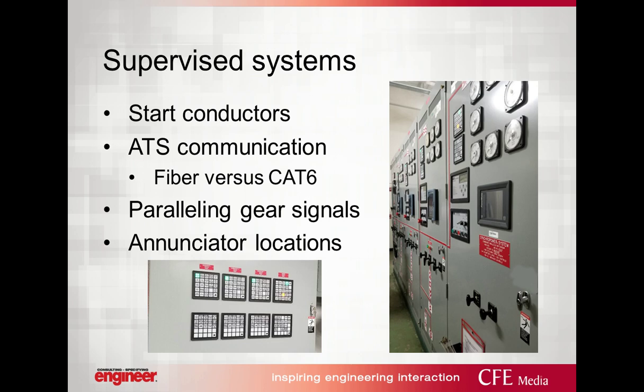NEC also has a new requirement for start conductors and them being supervised. Essentially, what designers need to do, you're used to pulling 2 wires back to the generator, keeping them separate. Now you're going to add a third. That third wire is to basically give the gear the ability to monitor voltage at the start conductors. Your ATSs, they're going to have switch position and source availability. Besides testing, you want extra cables to provide that data information to your paralleling gear.